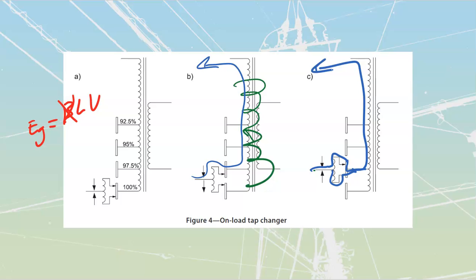It is going to operate incredibly fast. It's usually going to have a massive spring, with motor windings on there. The motor is going to coil the spring, and then there's a sear that's going to release, driving this thing from place to place inside here. Move it up, move it down, etc. There's going to be time in between each one - this boom as it moves over, then it has to wait, recoil the spring, and then boom, you move over to the next tap, etc.